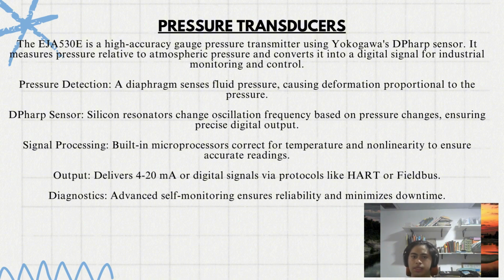Next, pressure detection. A diaphragm senses fluid pressure and deforms in proportion to the pressure. Next, as I mentioned just now, it uses the DPharp sensor. It is a silicon resonator that changes oscillation frequency based on pressure changes, ensuring a very precise digital output. In the unit itself, the EJA 530E has a built-in microprocessor that corrects for temperature and non-linearity to ensure high accuracy in all the readings.